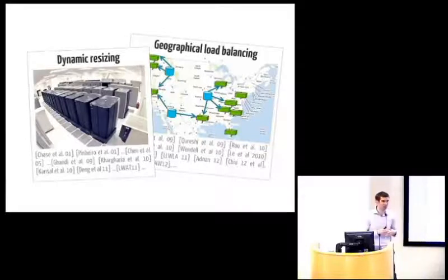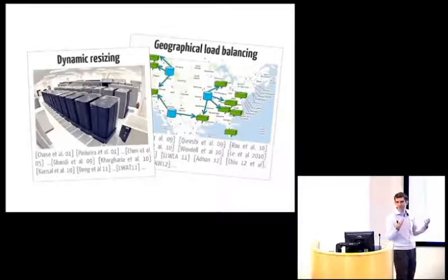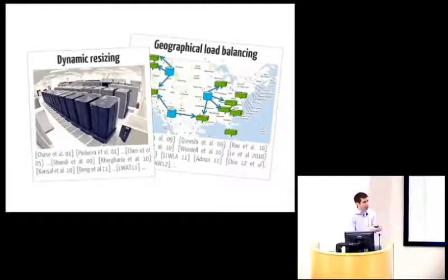And so you can think of doing the exact same problem, but now doing it in a high-dimensional space where you're not just optimizing one data center, you're optimizing a pool of data centers. And so now you have a choice. In addition to everything that's internal to one, you have a choice of where to route a request. So if you get a request from UIC and it comes to this proxy, you have lots of options for where to send it. And so you can optimize that, again, based on where there's sun for your renewables, where the temperature is right to be able to use outside air cooling. But of course, now you have the extra constraint of data availability and data mobility to make sure that you cache things appropriately to make all that possible.